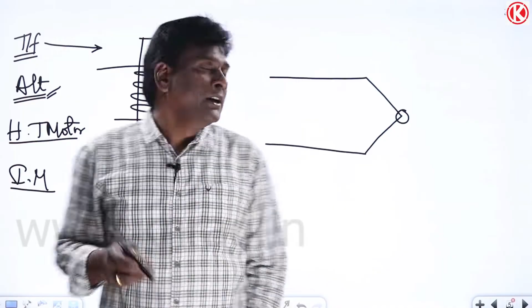So the moment sharp edge is there, what will happen? Ultimately, because of corona, such a huge corona may not occur, but because of corona, ozone will be liberated. Now that particular ozone may save our atmosphere, but in our machines, in transmission line, ozone will come, that's it. Nothing is going to happen because of ozone, maybe some corrosion or something like that.